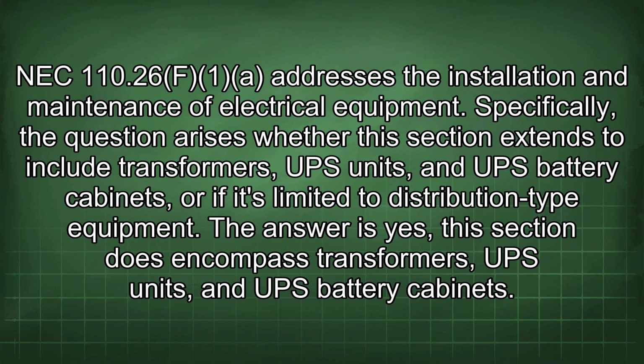NEC 110.26 only addresses the installation and maintenance of electrical equipment. Specifically, the question arises whether this section extends to include transformers, UPS units, and UPS battery cabinets, or if it's limited to distribution-type equipment. The answer is yes, this section does encompass transformers, UPS units, and UPS battery cabinets.